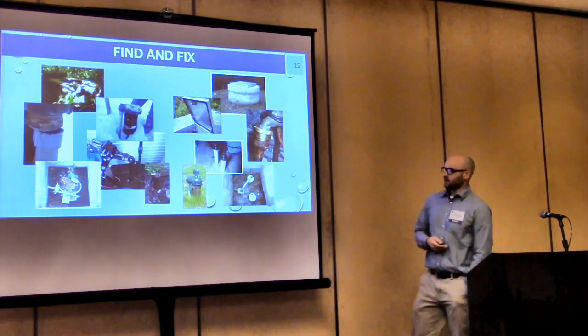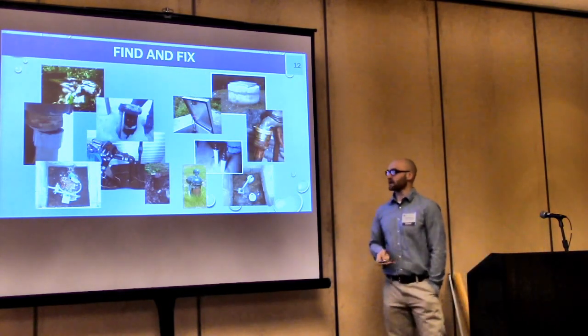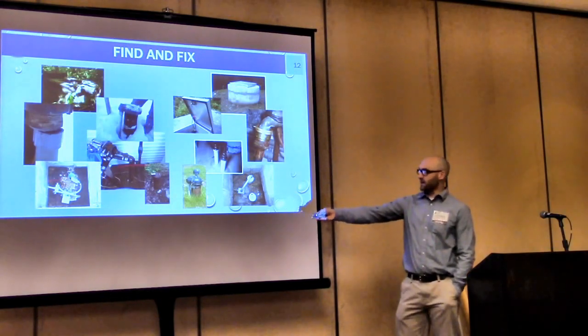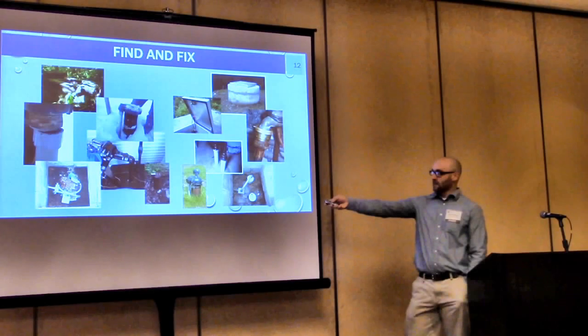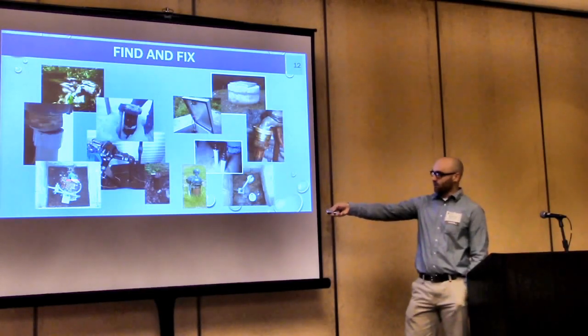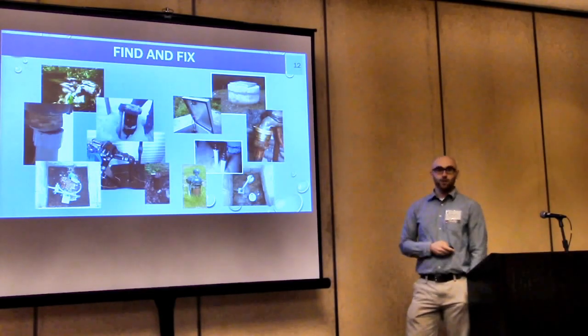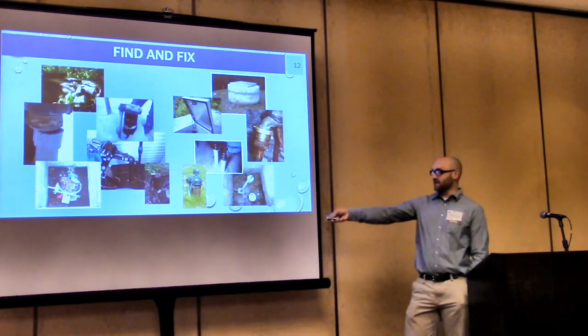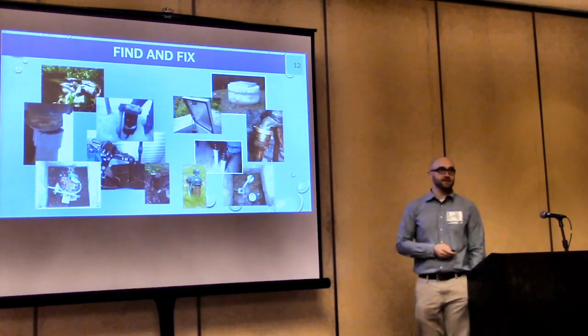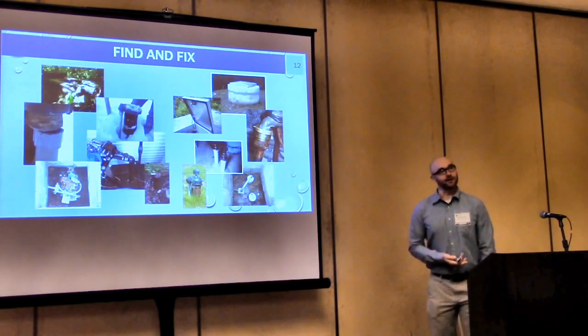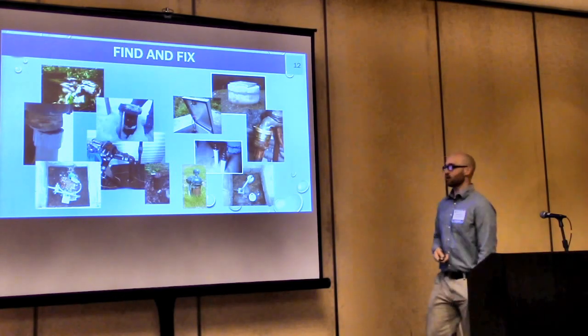It also assesses breaches in storage tanks. So these 2 pictures right here, this one you can't see as well, but that's an access to a storage tank. So you open the hatch and you can see the probes for the level controls. That's just an open conduit. You can't really see it, but that's a rat's nest. And then this is just crumpled up, chewed up little leaf bits. So not ideal. Little stuff can get into your drinking water system and create havoc.